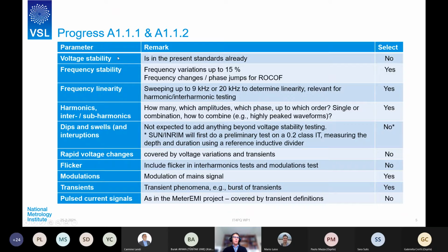I will go along this list. So the voltage stability, we decided actually is already in the present standards, so we don't have to consider that. Next one is frequency stability. In literature, we've seen frequency variations up to 15% beyond the nominal value. So we will need to do frequency change tests and also phase jumps, which are relevant for rate of change of frequency testing as defined for PMUs. So we will definitely do that. Also, frequency linearity is relevant because several of the ITs are non-linear with respect to frequency. So what we have in mind is to sweep up to 9 kilohertz or perhaps 20 kilohertz. Officially, our limit in this project is 9 kilohertz, but we know that some standards already mention 20 kilohertz, so perhaps we should do that as well.